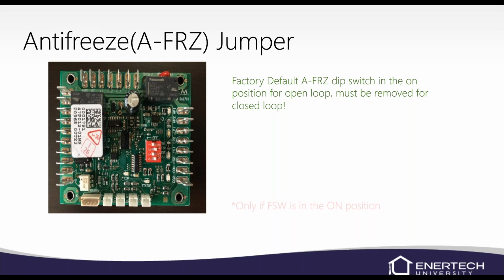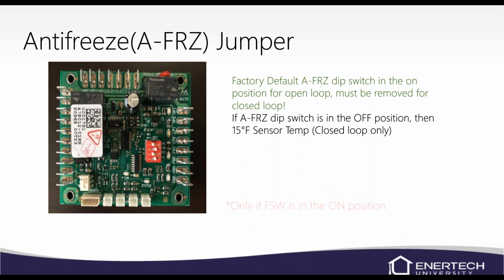Antifreeze jumper, so that is the A-FRZ. The factory default, the switch is in the on position. When the dip switch is in the on position, that thermistor is looking at 30-degree freeze protection. So an open loop or a closed loop with no antifreeze in it. So we're saying, hey, at 30 degrees, that's going to freeze, so we're going to lock it out. Obviously, we don't want water to freeze. It breaks things. So with that dip switch in the off position, now we're saying, okay, we have a closed loop and we have antifreeze in the system. So we normally have antifreeze protection down to 15 degrees. So now that that switch is in the off position, that sensor is now looking at 15-degree freeze protection.